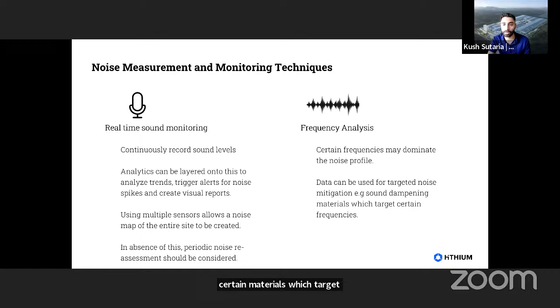If you can't do real-time monitoring, then doing the baseline study and repeating it every so often so you can collect data on how noise actually behaves in operation and evolves over time is pretty important. Not just overall noise, but also frequency analysis. If you're implementing soundproof enclosures or walls, you might want to use certain materials that target certain frequencies, because that's more effective. As Darrell mentioned, these systems are expensive, so you want to use your capital wisely.